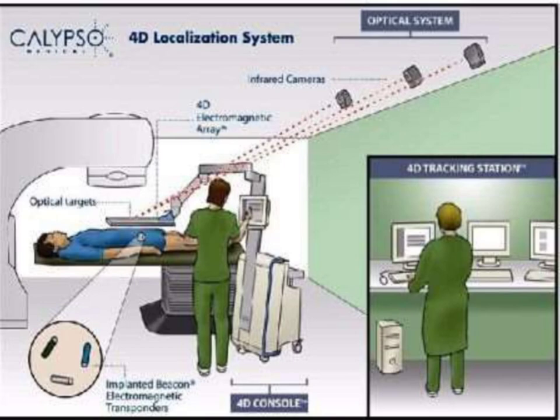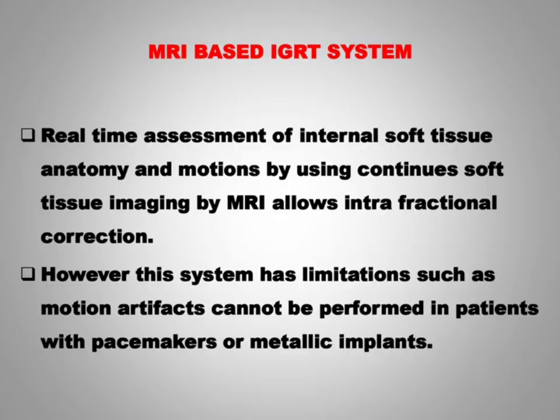Because of organ motion the beacons will move, so if we intend to give radiotherapy to that moving organ, the beacons will also move and will be tracked by the electromagnetic imaging system. Beacons need to be placed in the tumor via a minimally invasive procedure, but their presence produces artifacts, particularly in the MR images, and that's why its use is limited to prostate cancer.